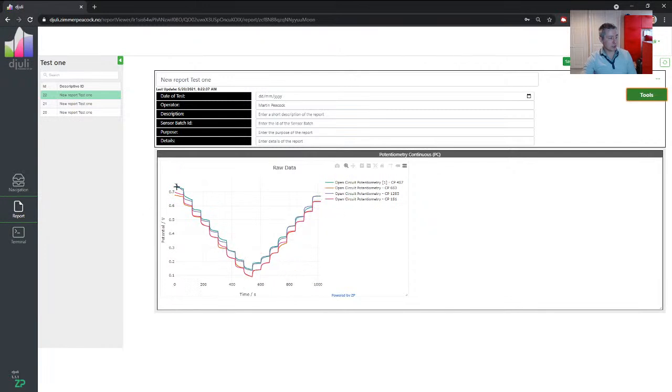You can essentially see the way our guys work, that they've gone into the lab. So this is time. They've started 4 sensors in parallel, and they've tested at pH 2, pH 3, pH 4, pH 5, etc. And the voltage has changed accordingly. I might just adjust something quickly.